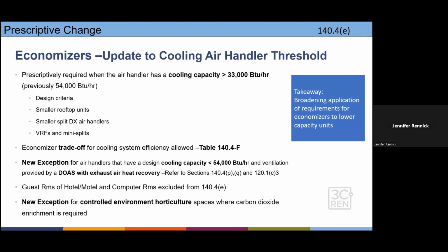Same concept with economizers, now specifically addressing what's allowed for economizer trade-offs and exceptions that are provided when you're using a DOAS, dedicated outside air system, with exhaust heat recovery. The big takeaway is that they're broadening the application of requirements for economizers to lower capacity units.